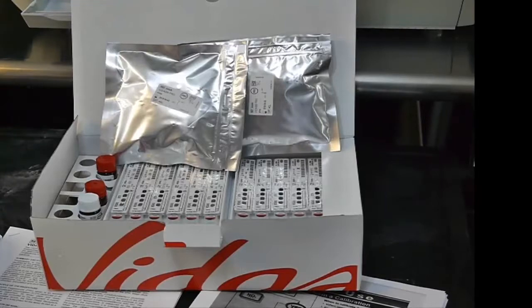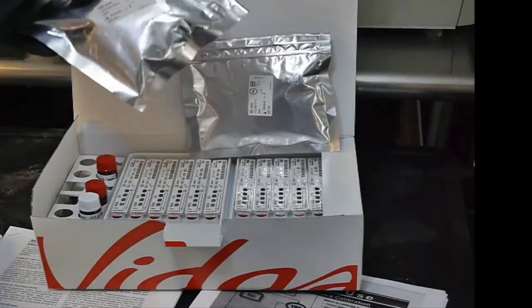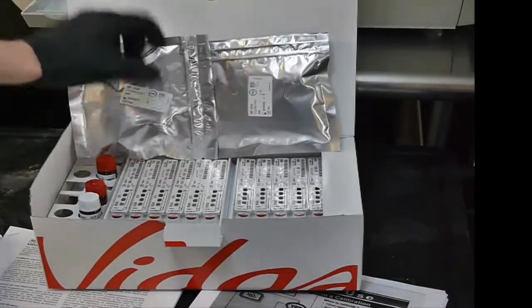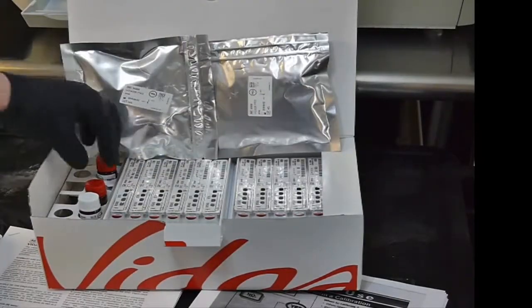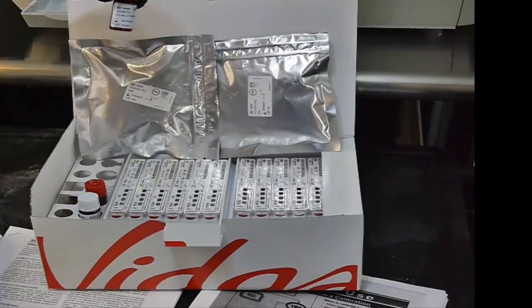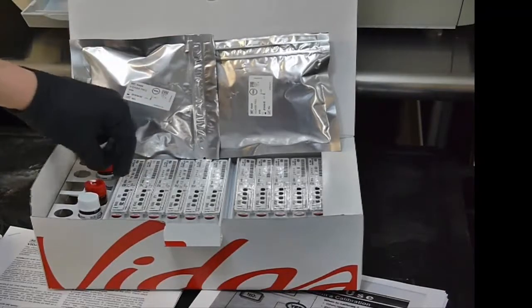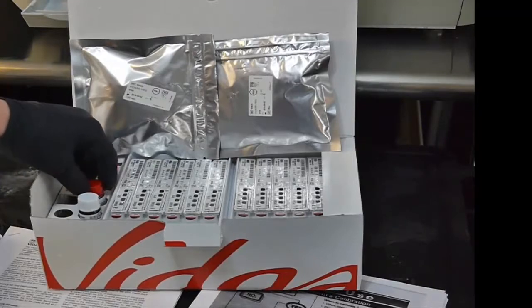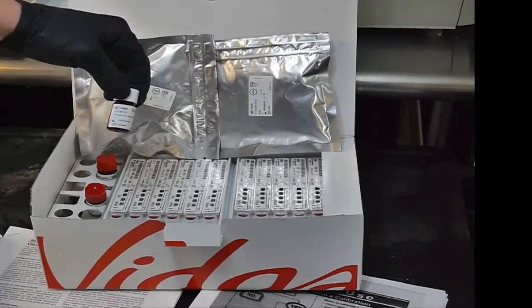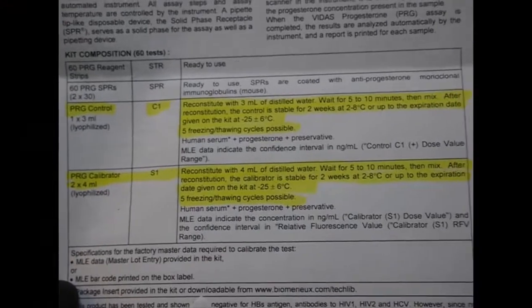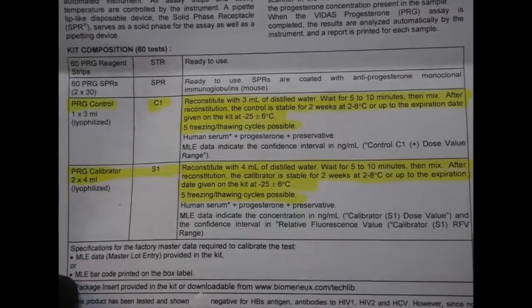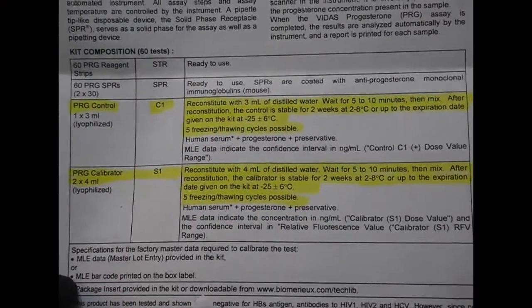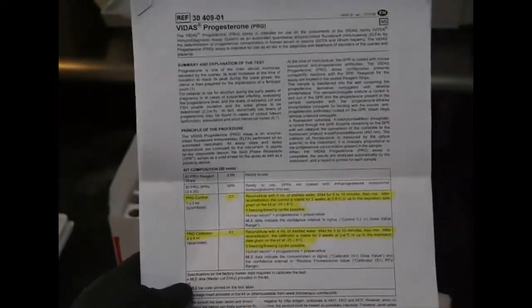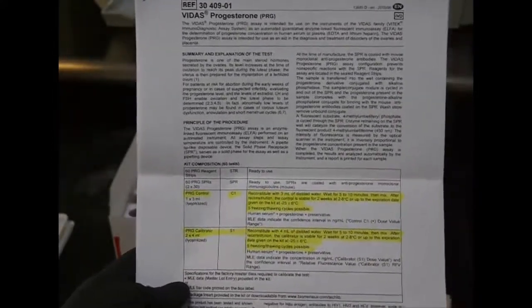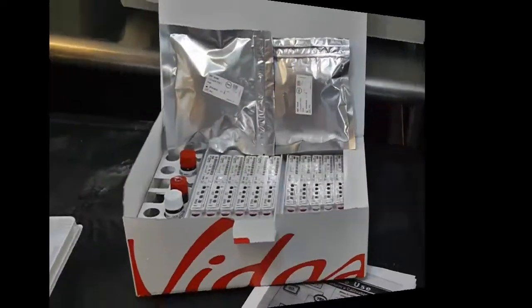Each 60 test count kit contains 2 bags of the SPR, or solid phase receptacles, 60 of the test unit strips, 2 vials of the S1 or calibrator. S1 stands for standard level 1, and 1 vial of your control substance. Your standard and your control will come lyophilized and will need reconstitution with distilled water. On the first page of the insert sheet for the progesterone assay are the instructions on how to do this.